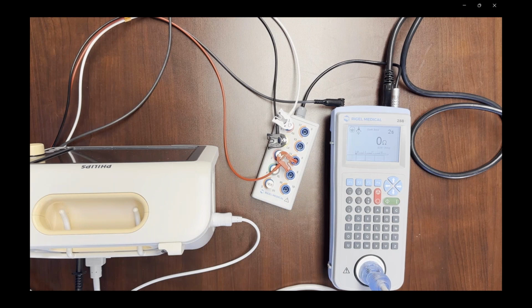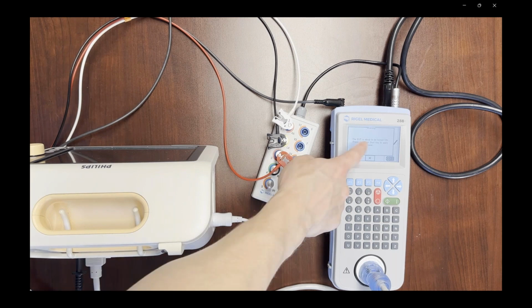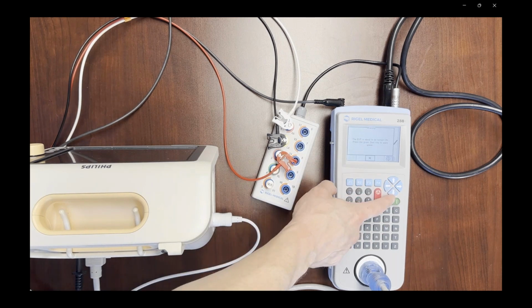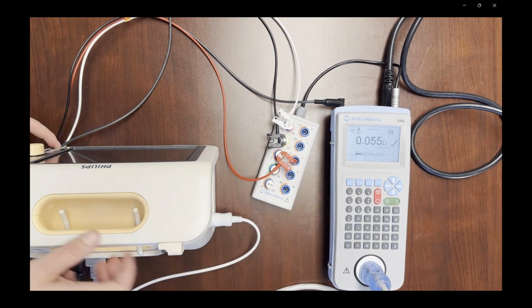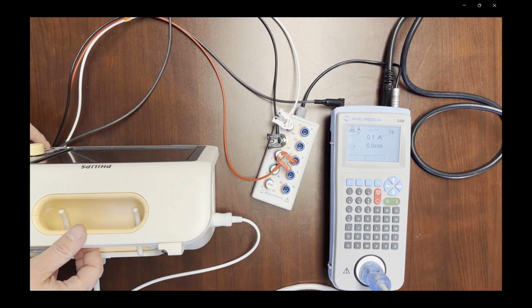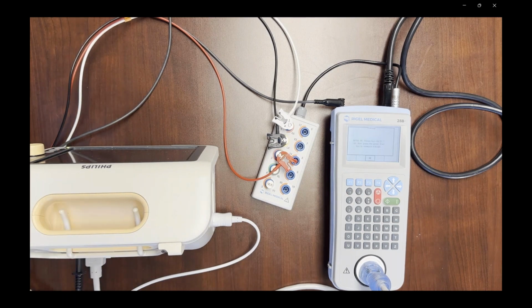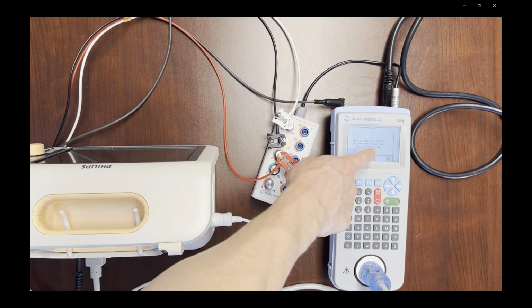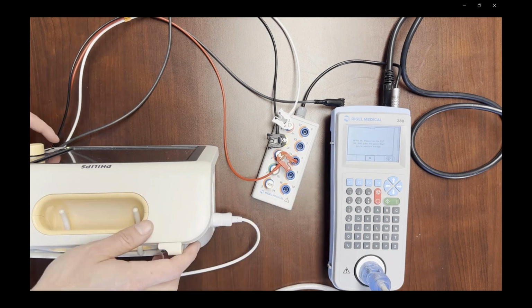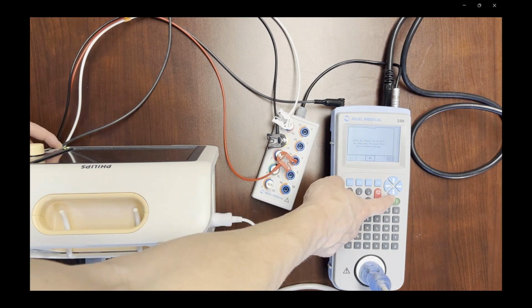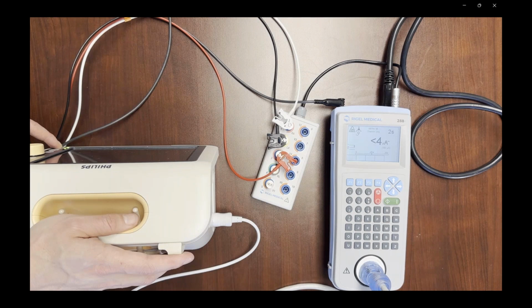And it's just going to run through a series of tests to make sure, as long as the values that are measured by the 288 are within the NFPA 99 limits, it will just run through sequentially each of the tests. If it does encounter a failure, a prompt will come up on the screen to ask if you're happy to proceed with that failure, and it will be inputted into the report, or it will ask you to repeat the test. Sometimes there's an issue with the ground bond lead, then it does give you the option to restart the test and try again.